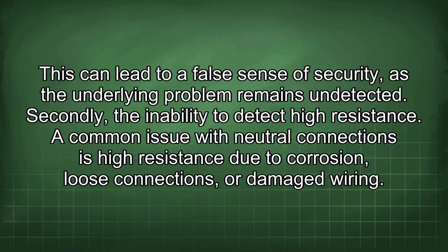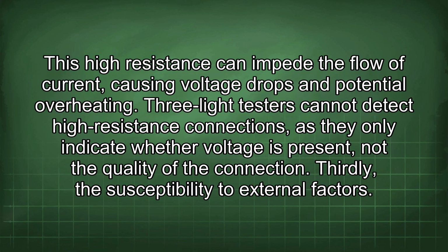Secondly, the inability to detect high resistance. A common issue with neutral connections is high resistance due to corrosion, loose connections, or damaged wiring. This high resistance can impede the flow of current, causing voltage drops and potential overheating. 3-light testers cannot detect high resistance connections, as they only indicate whether voltage is present, not the quality of the connection. Thirdly, the susceptibility to external factors.